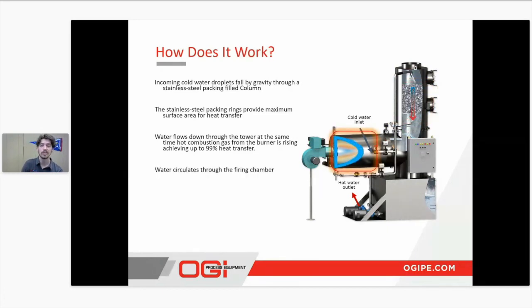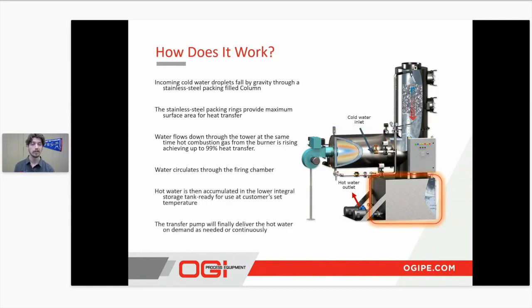Additionally, as the burner is firing, water is going to be circulating through our firing chamber. As long as the burner is on and operating, this water will be cycling through. This will be here to protect from any hot spots on the QuikWater, as well as keep that water cooling the outside of the jackets. And finally, that water is going to be gravity fed down through the QuikWater. As it passes through the packing, it's heated up by that combustion gas, collecting in our internal reservoir tank, ready to be pumped out to your solution whenever you need.